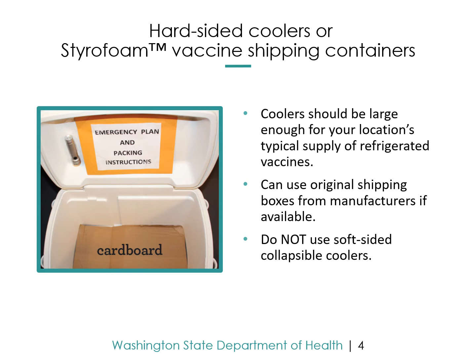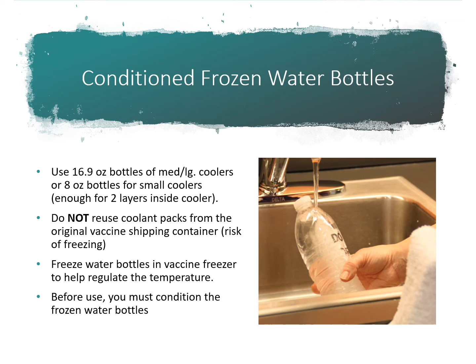Conditioned frozen water bottles: use 16.9 ounce standard size bottles for medium to large coolers or 8 ounce bottles for smaller coolers, but make sure there's enough for 2 layers inside the cooler. Do not reuse coolant packs from the original vaccine shipping container, for that can cause a risk of freezing. Freeze water bottles in the vaccine freezer to help regulate the temperature. Before use, you must condition the frozen water bottles.